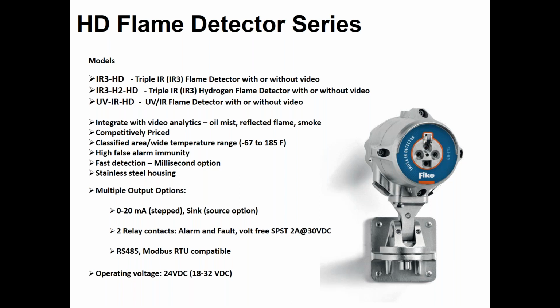There's an RS-485 connection to the detector to view live video, download video from the detector itself. The detector has flash memory that is being monitored, that is recording 24/7, tracks events. When there's an event, it's tagged. A minute prior to the event is recorded, plus 3 minutes after the event. And that information can be downloaded through the RS-485. The RS-485 can be daisy chained through the detectors, and you have a central location for connection to the RS-485.